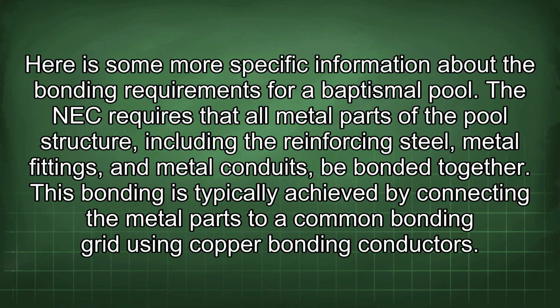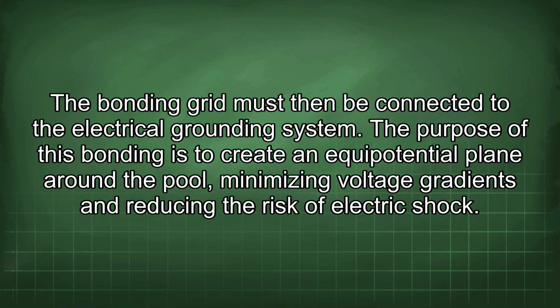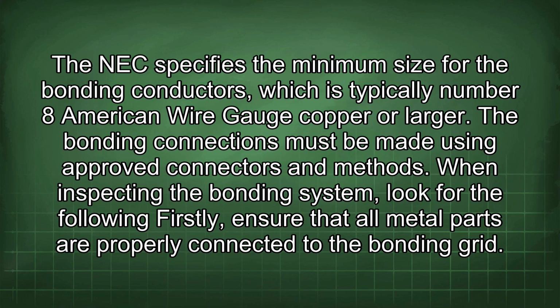Here is some more specific information about the bonding requirements for a baptismal pool. The NEC requires that all metal parts of the pool structure, including the reinforcing steel, metal fittings, and metal conduits, be bonded together. This bonding is typically achieved by connecting the metal parts to a common bonding grid using copper bonding conductors. The bonding grid must then be connected to the electrical grounding system. The purpose of this bonding is to create an equipotential plane around the pool, minimizing voltage gradients and reducing the risk of electric shock. The NEC specifies the minimum size for the bonding conductors, which is typically number 8 American wire gauge copper or larger. The bonding connections must be made using approved connectors and methods.